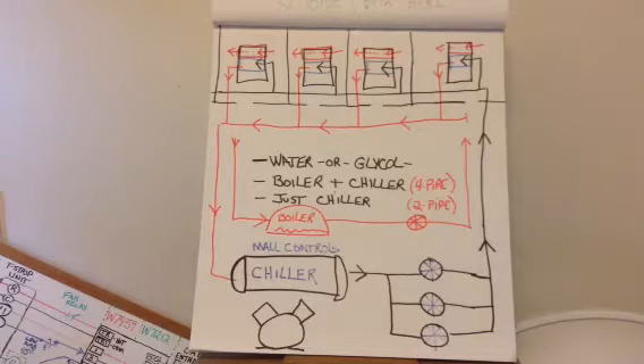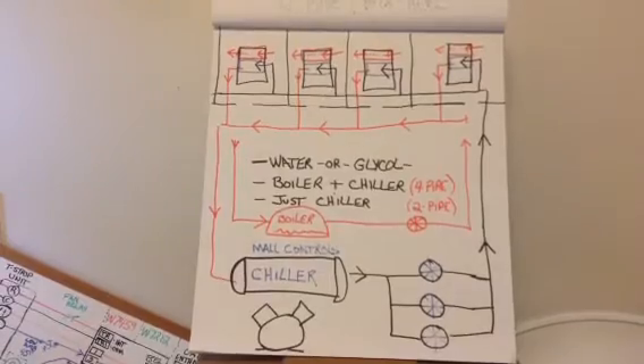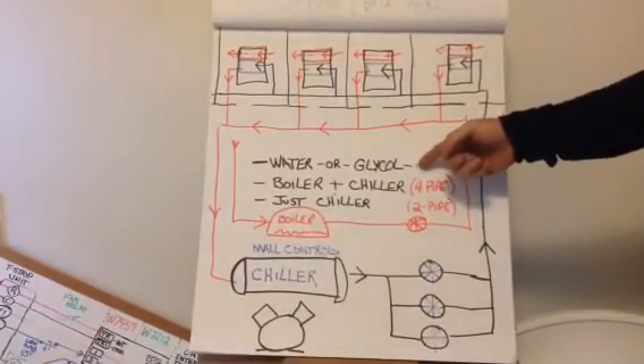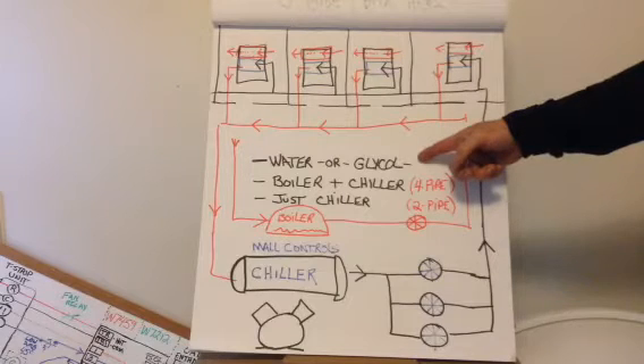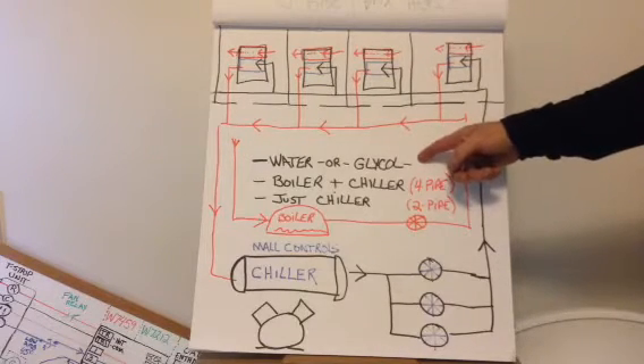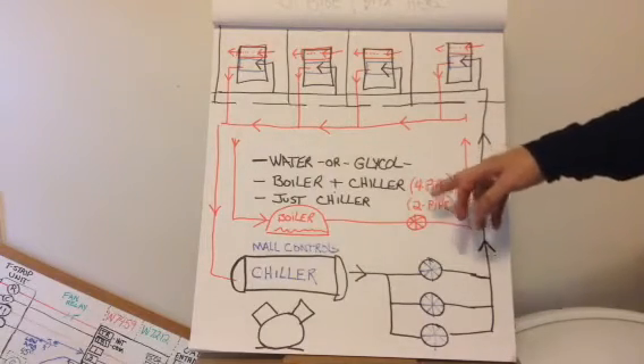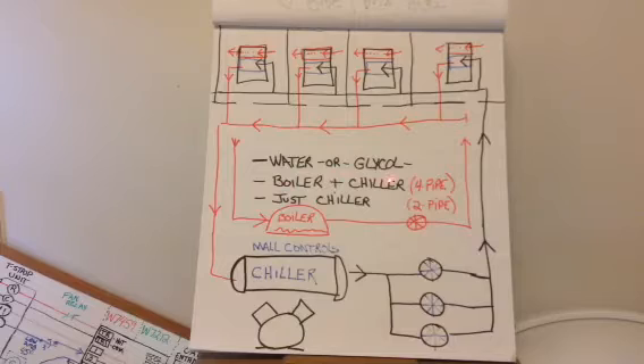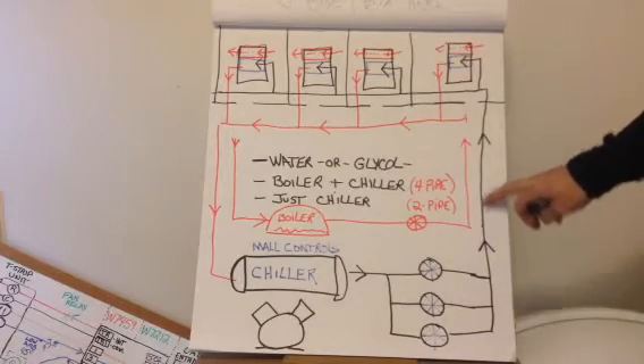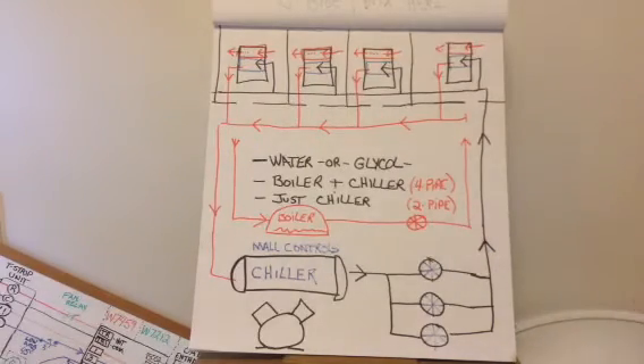Basic logic or basic terminology I want to talk about a little bit, guys, is water or glycol. You need to pay attention to that. Again, this is the mall's decision, not yours, not mine, not ours. The other thing you need to pay attention to is do they have a boiler and a chiller, or do they have just a chiller? If they have a boiler and a chiller, they might have a 4-pipe system where they have a chilled water supply pipe, a hot water supply pipe, a chilled water return pipe, and a hot water return pipe to the boiler. That is what we would typically call a 4-pipe system.